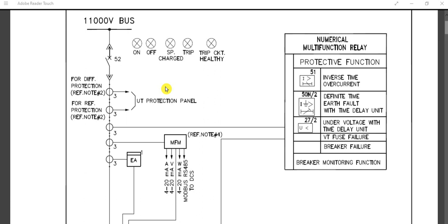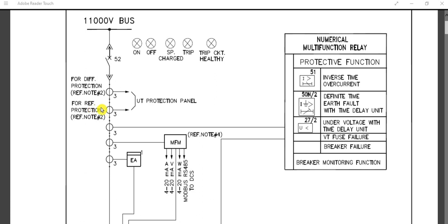For protection, since this feeder is coming from a unit transformer, we have a differential protection relay (87). For this differential protection, we need a CT (current transformer) on the 11kV switchgear side — this is the differential CT, which will be connected to the 87 differential relay. Another set of CTs is located on the upstream side. The second CT is for REF (restricted earth fault) protection.